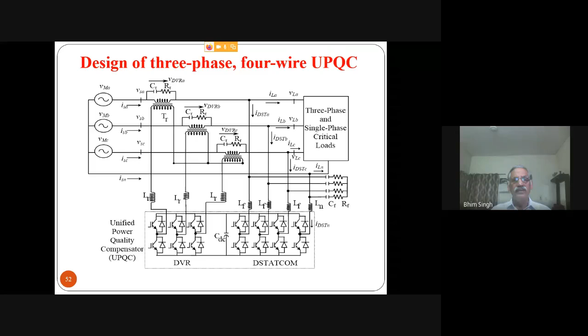Okay, the DC link voltage should be slightly higher than the line voltage, or it should be twice the phase voltage, as one has given in his book. So from the line voltage we calculate the phase voltage by dividing by √3, take the RMS to peak, then twice this, and then the modulation index. So we get the DC link voltage selection and we round it off. If we get, let's say, 670 volt, we round off to 700 volt, for a 415 volt system, depending on how you are selecting.